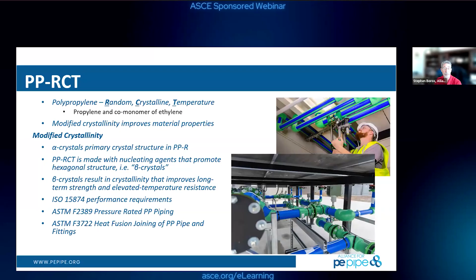So on the PPRCT side, it's not just the material. The materials do have PPI ratings, and then they have what's called MRS—that's under the ISO system—for long-term strength rating of their materials. So there are materials listed by PPI, just as there are for polyethylenes and every other type of thermoplastic. The MRS is typically rated at 20 degrees C, and then you have to do what's called a categorized required strength when you go up to higher temperatures. So you can see these are all long-term stress-rated materials to make sure you have that long life in the application.